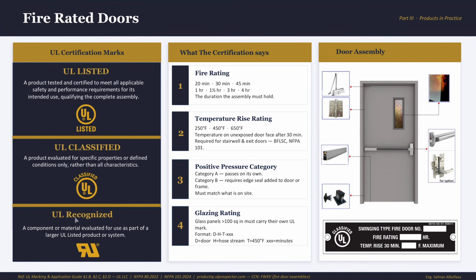And finally, UL recognized. This mark applies to components intended to be integrated into a final product. These components cannot be used on their own, but must function as part of a broader system. Let's say the door closer will be UL recognized and it will be part of the whole assembly, like a hinge or an intumescent seal, individual parts that go into the door assembly. They cannot do the job alone, so they are recognized as part of a bigger assembly. Going back to the iPhone, the battery of the iPhone is UL recognized, just like the battery of the control panel. It cannot make a phone call on its own. It has no function by itself. It cannot detect fire by itself. So it is tested and certified to work safely inside a larger product.